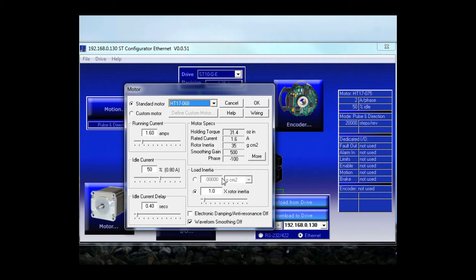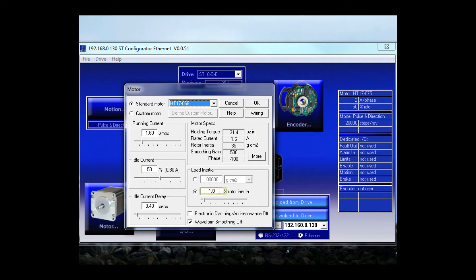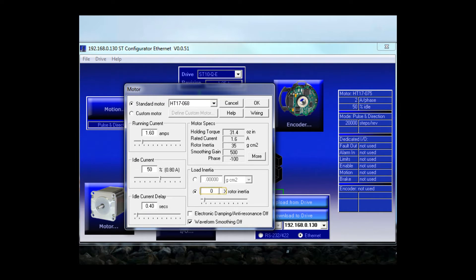One more thing while I'm in the motor dialog, I need to set the rotor inertia. These drives contain a very sophisticated anti-resonance and electronic damping algorithm. And that requires a motor model to be running inside the DSP chip. The one thing that that motor model can't figure out on its own is how much load inertia is connected externally. Well, I don't have anything connected to my motor, so that would be 0x rotor inertia.